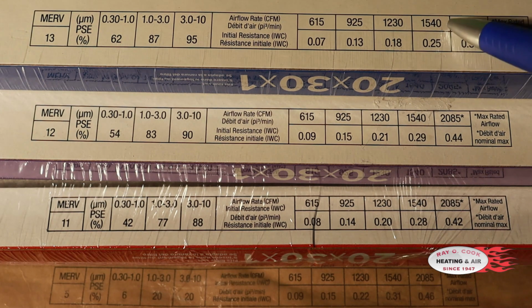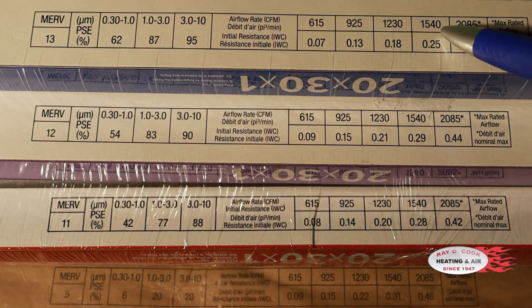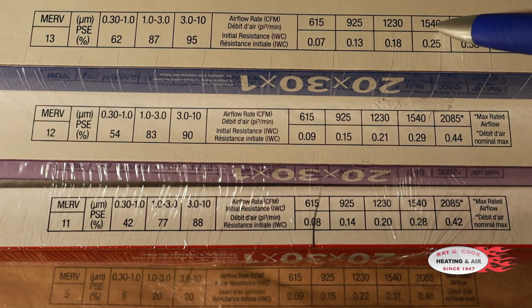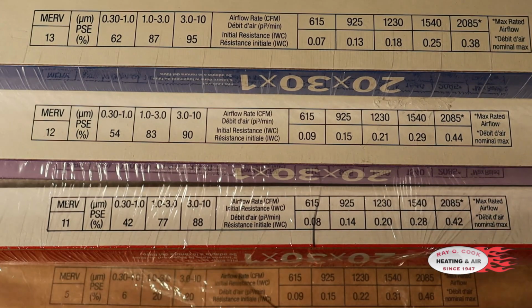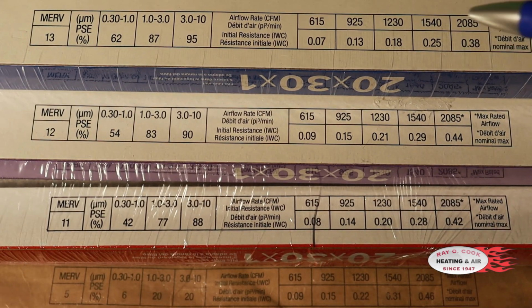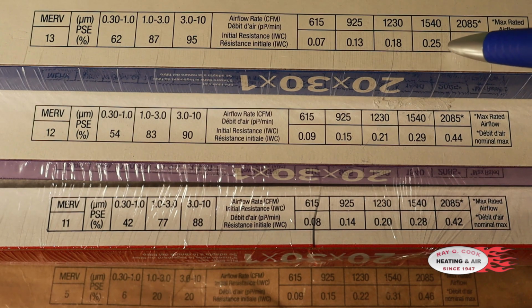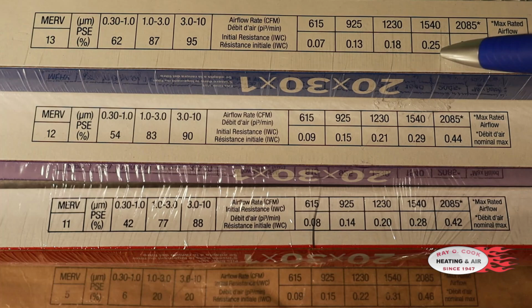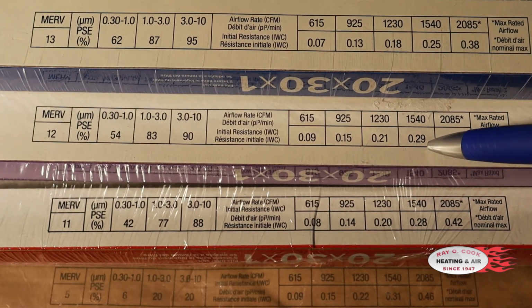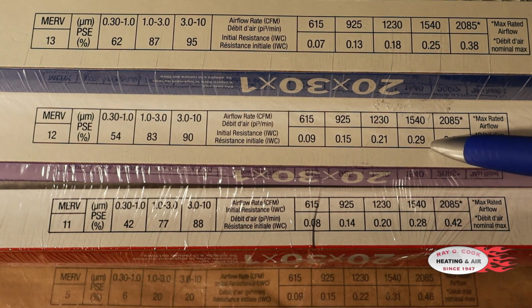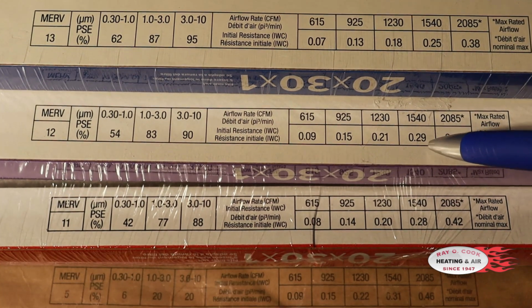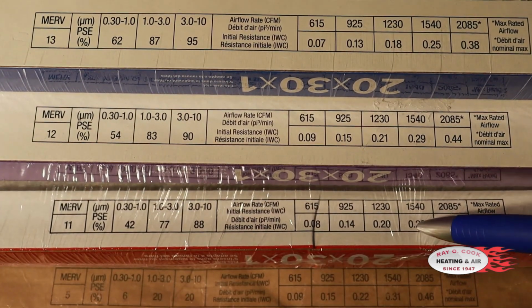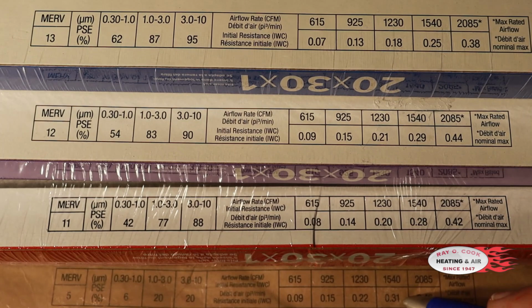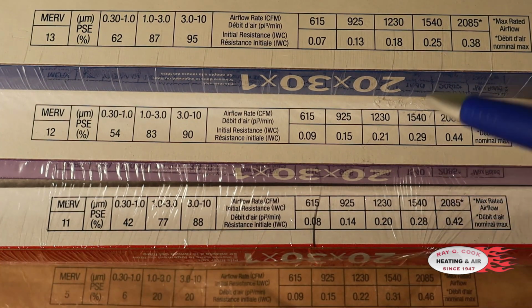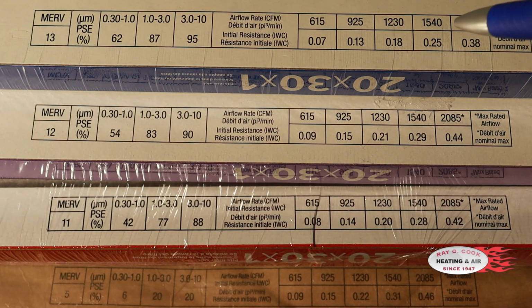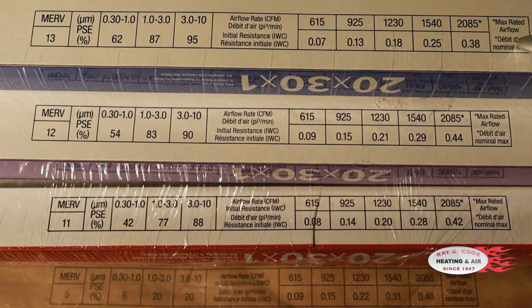For fun, let's look at a 4-ton unit. So 400 CFM times 4 ton, our airflow rate, they're giving us 1540 on this rating. They're all 1540s. Okay, the 1540 is going to be close enough to 1600 CFM. This filter right out of the box, way too restrictive. The next one down, MERV 12, it's rating at 0.3 clean. We don't want to be anywhere near 0.2 max. 0.28 on the MERV 11, 0.31 on the MERV 5. So on a 4-ton unit, it is virtually impossible to move enough air through this filter and be correct.